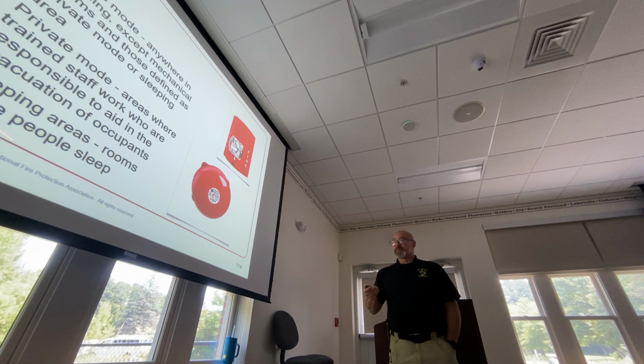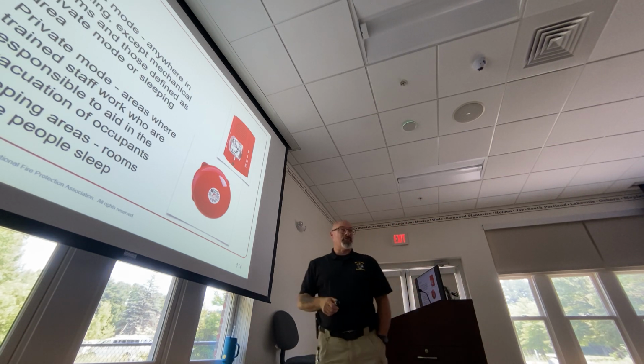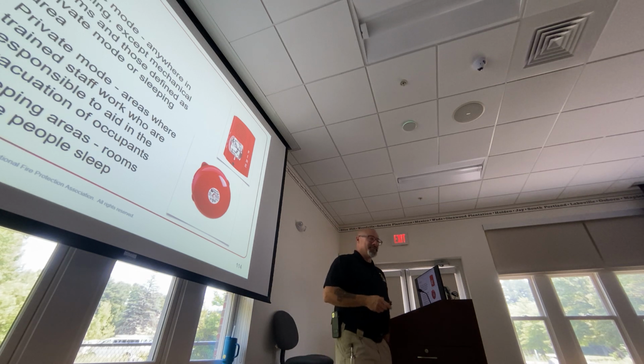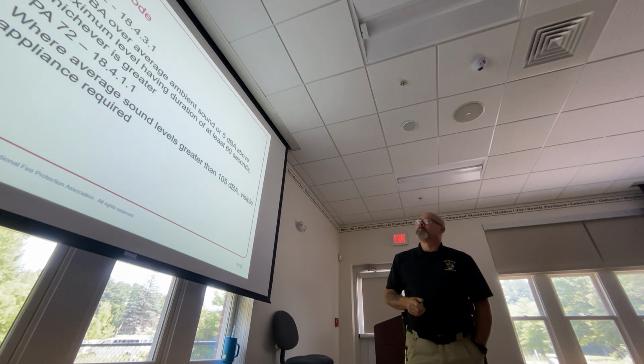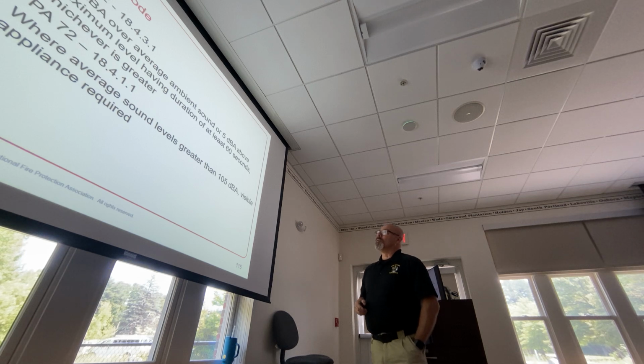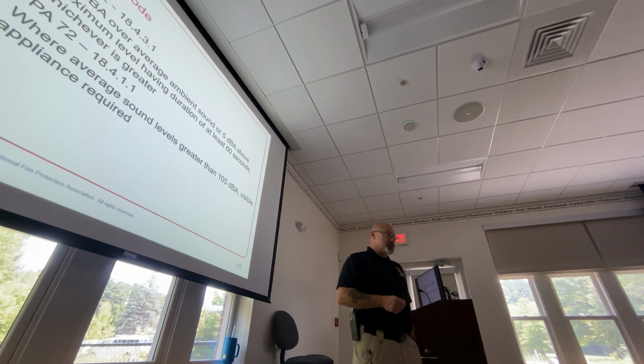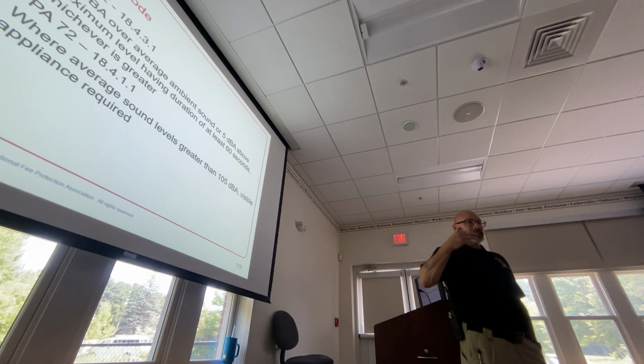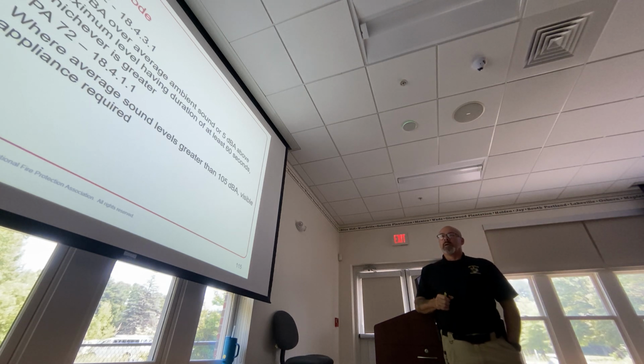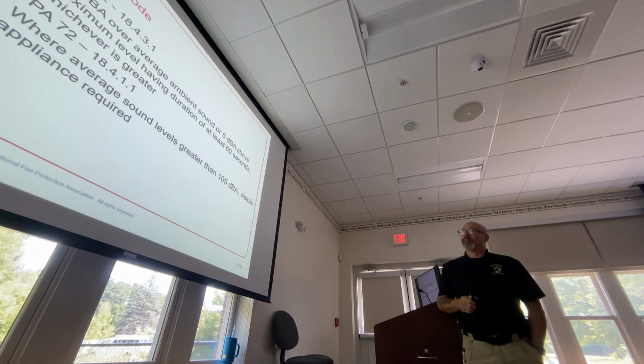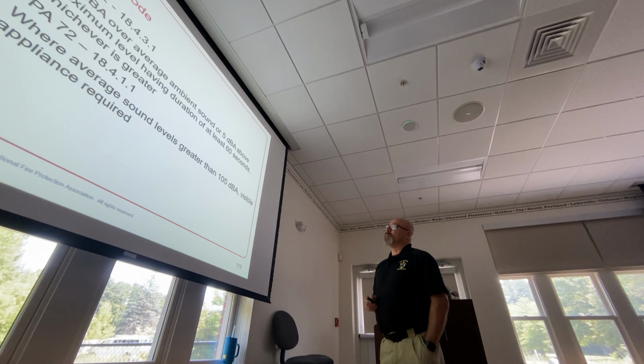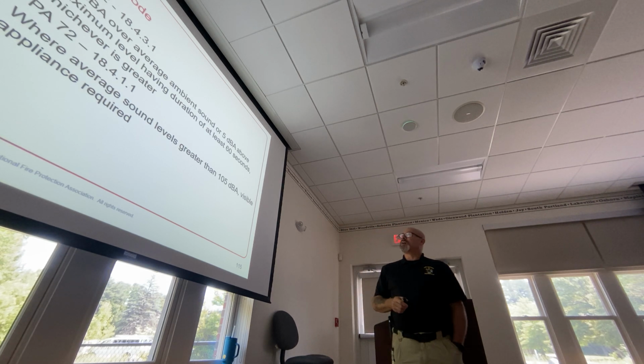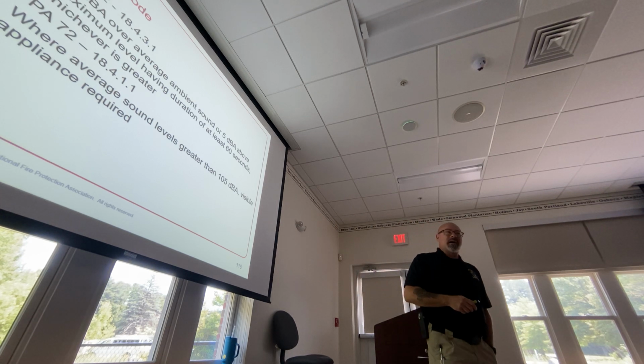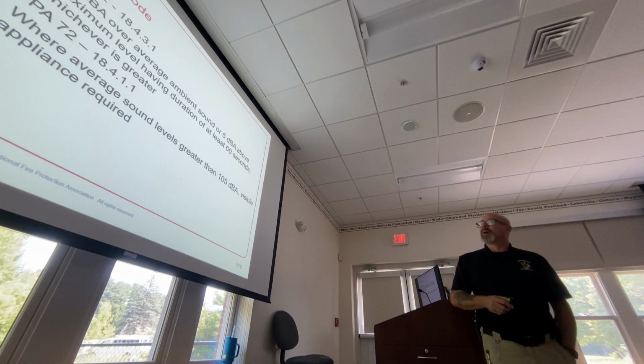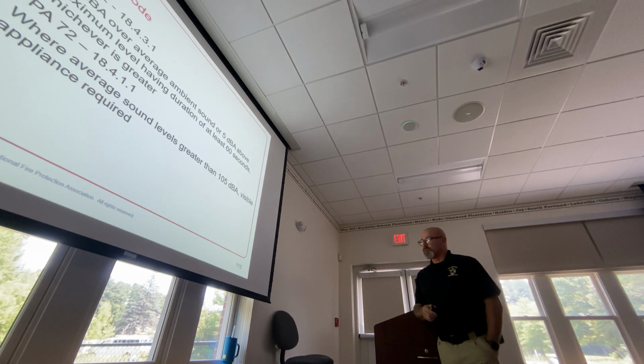They define sleeping areas as rooms where people sleep. That's a good one. In public mode, fire alarm systems are required to notify in the audible mode at 15 decibels, dBA, over the average ambient sound, or 5 decibels above the maximum level having duration of at least 60 seconds, whichever is greater.